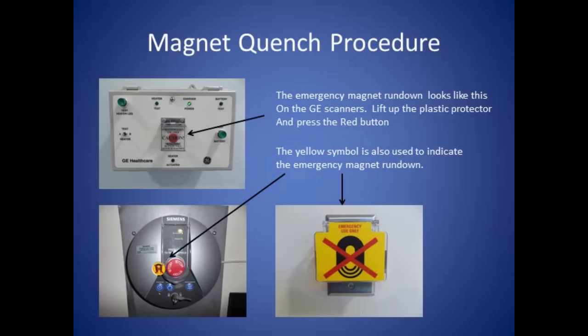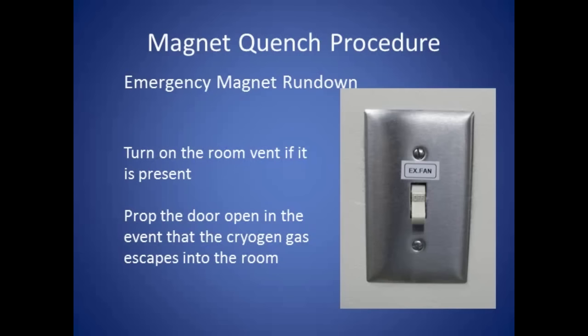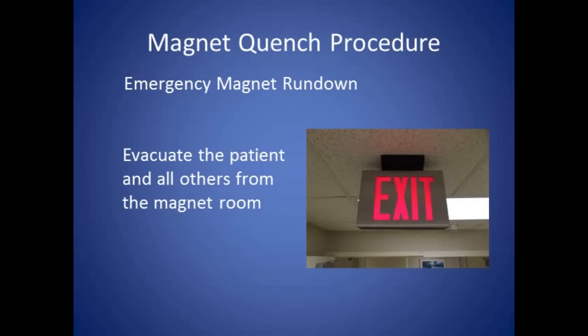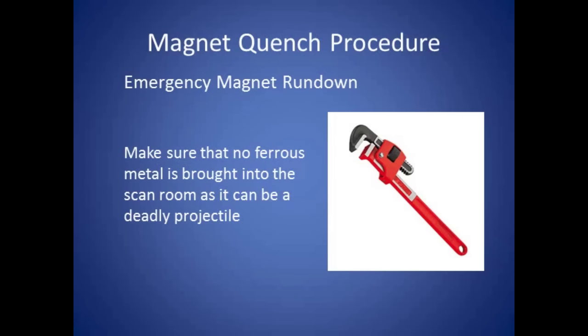To begin the emergency magnet rundown procedure, turn on the room vent if it is present. Prop the door open in the event that the cryogen gas escapes into the room. If there is a patient in the MRI scan room, evacuate them along with all others from the area and secure the room. Make sure that no ferrous metal is brought into the MRI scan room before the magnet is quenched, as it can become a deadly projectile.